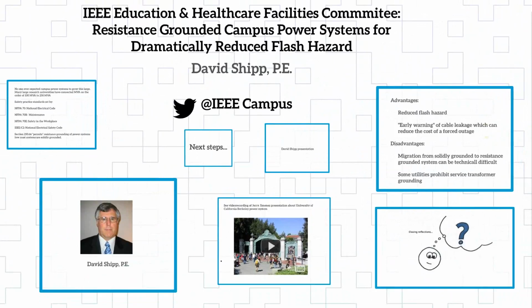Go ahead. With a little bit of design and the grounding issue, I can improve the safety, I can improve the continuity, and save money in the process just by how I judiciously put it together. And that's really the bottom line. I've worked through all this and scratched my head on how to solve problems like this in the past. You know, Tammy's been looking at a lot of the arc flash stuff and working on the arc flash incident energy issues. And so you know that if we go to a small kVA transformer, the incident energy goes down dramatically. And we can work around and make those things work.